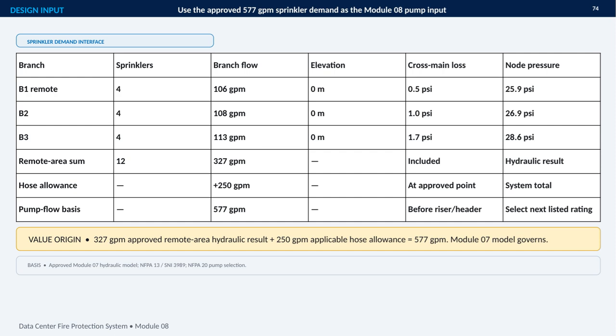The pump flow basis is taken before the riser and header, and the instruction is to select the next listed pump rating above this requirement. The governing basis is the approved Module 07 model, together with NFPA 13, SNI 3989, and NFPA 20 pump selection requirements. This creates a clear interface between the sprinkler demand calculation and the pump selection step.